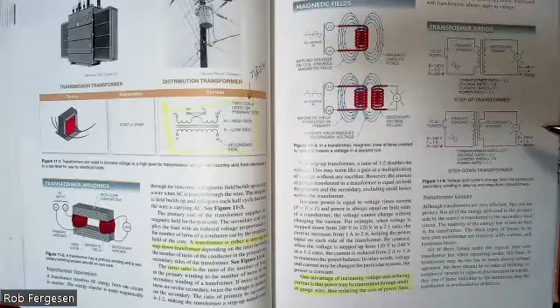And what I do in this case, I'm going from a low voltage, 120 volts, to a much higher voltage, 240 volts, by having twice as many turns on the secondary. Step down goes in the opposite direction. So twice as many turns on the primary as the secondary. So it's a 2 to 1 transformer ratio. My voltage ratio is 2 to 1, which means it cuts the voltage in half. My current ratio is doubled: by cutting the voltage in half while maintaining power consistent, my current needs to double. This is more typical of a control transformer. If I want 120 volts output, 120 volts AC is a pretty typical US control power that I would use for my switches and push buttons. So this is a more typical drawing for a control transformer.